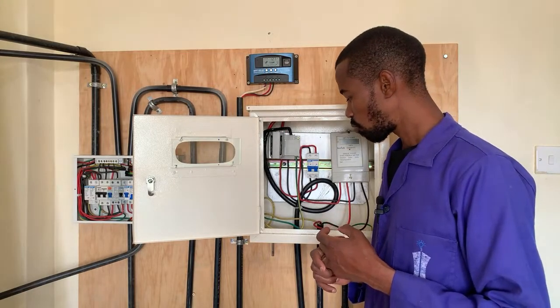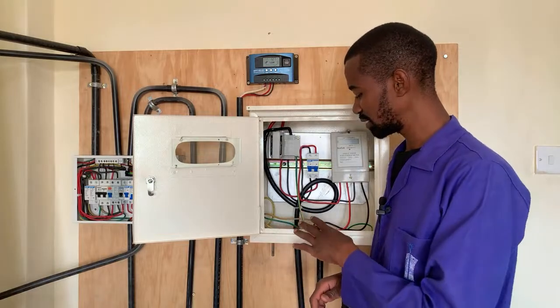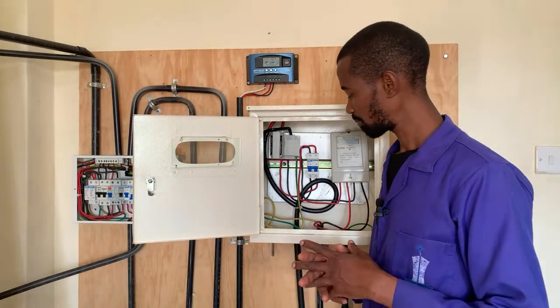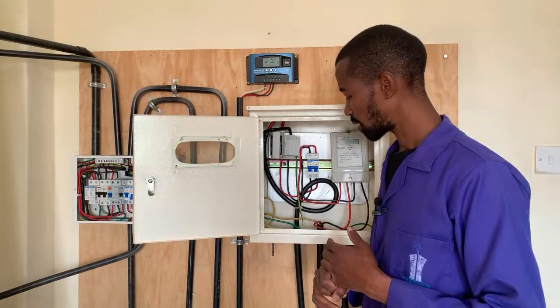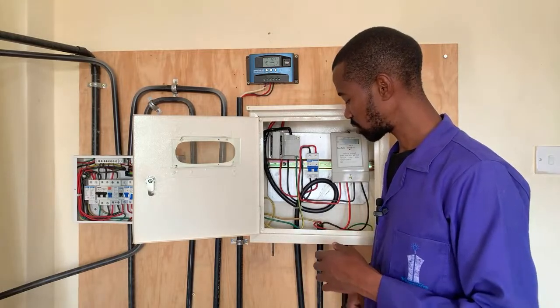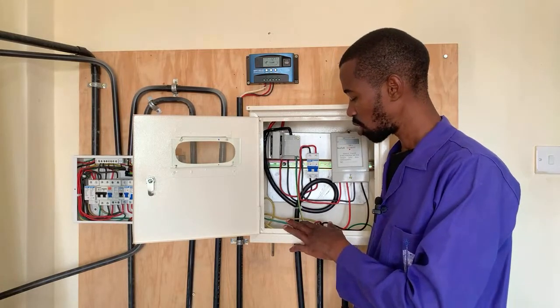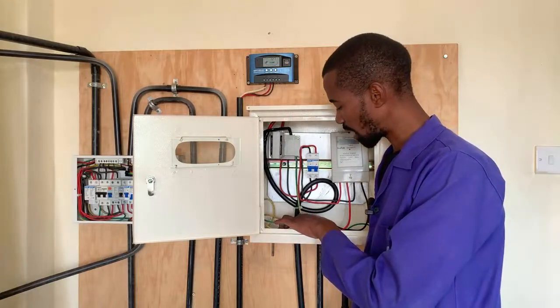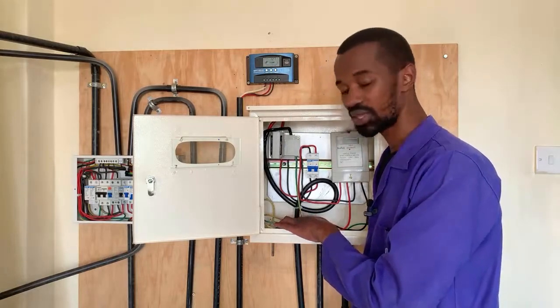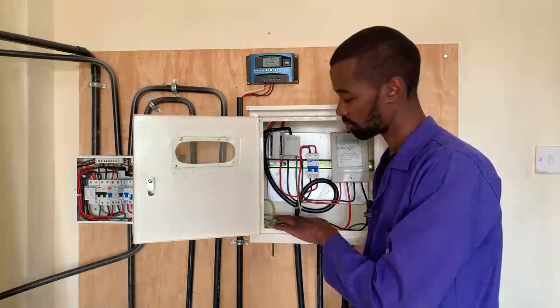So that issue is very important. We have determined that indeed that home has a problem. So what you do, for instance in that scenario, at the meter box level, we have to first check on the integrity of our earth connection.